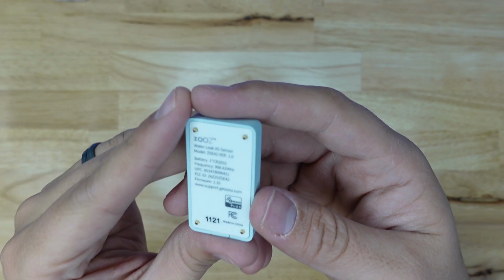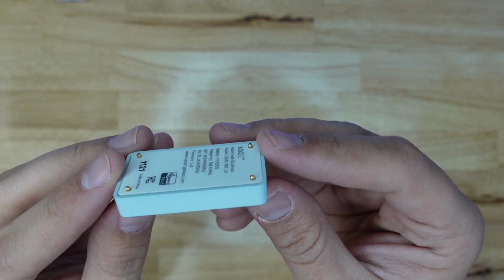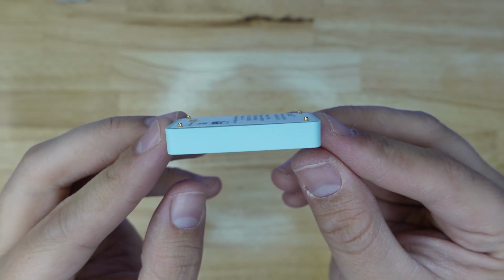Water leak sensors basically work by having two or more conductive electrodes or probes that are exposed to water. Since most water, besides deionized and distilled water, is conductive, when it comes in contact with these electrodes, it closes the sensing circuit, letting the device know that water has been detected. Even a damp paper towel has enough water in it to close that loop.